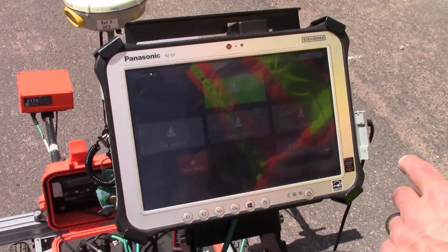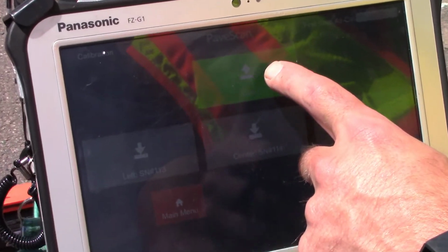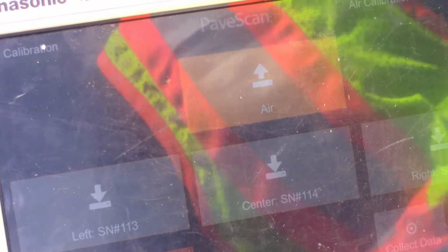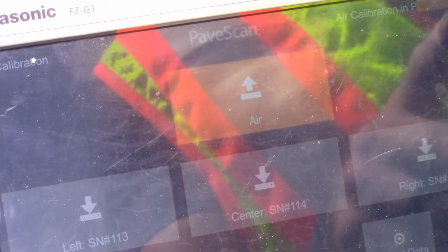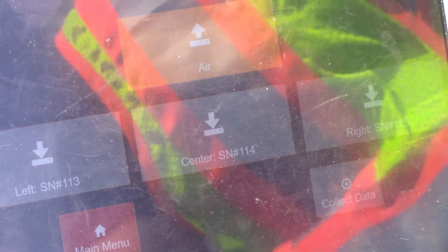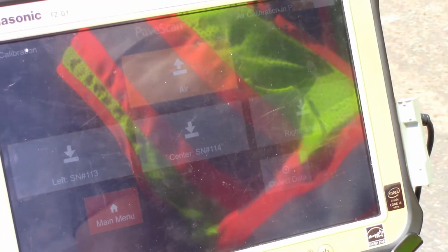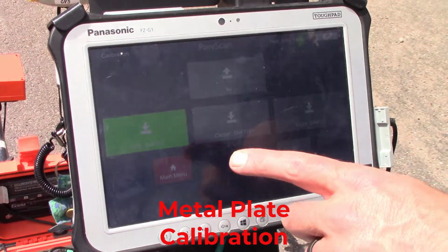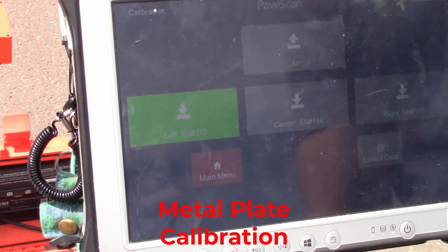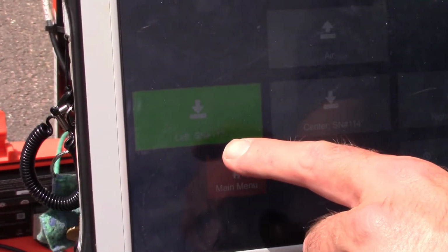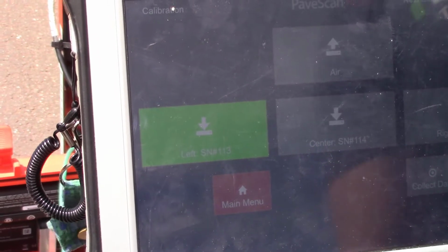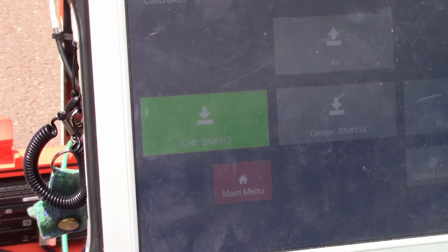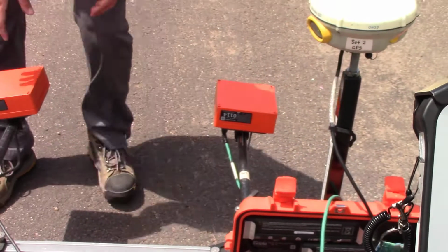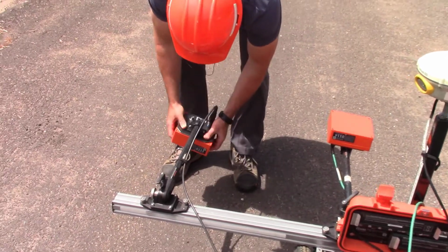So we'll come back here to our software and simply press the green button called Air. And you'll know it worked when it turns orange and you see air calibration is in progress here. Once that bar goes to the end, you know that this step has completed. You'll now notice that the green button has moved down to the bottom. In this case, we're starting with the left sensor when doing our metal calibration. That tells us we need to go back to our sensors and turn them back so that they're facing toward the pavement.